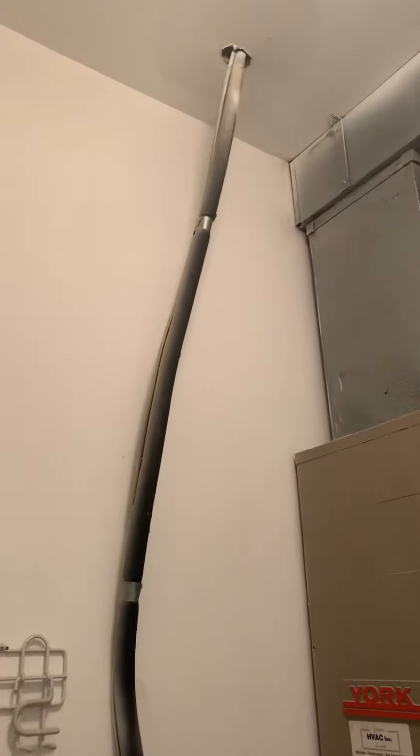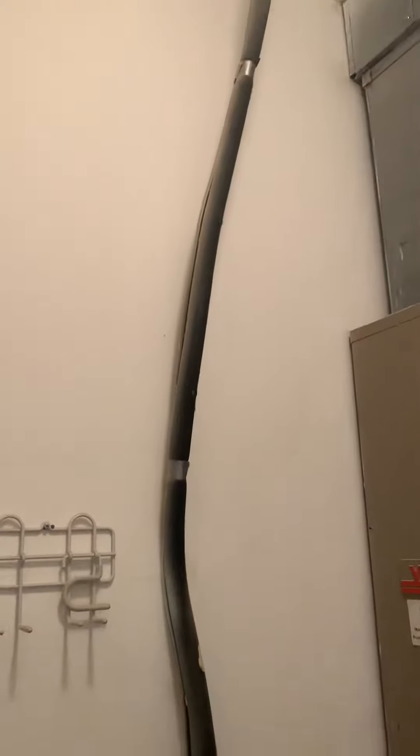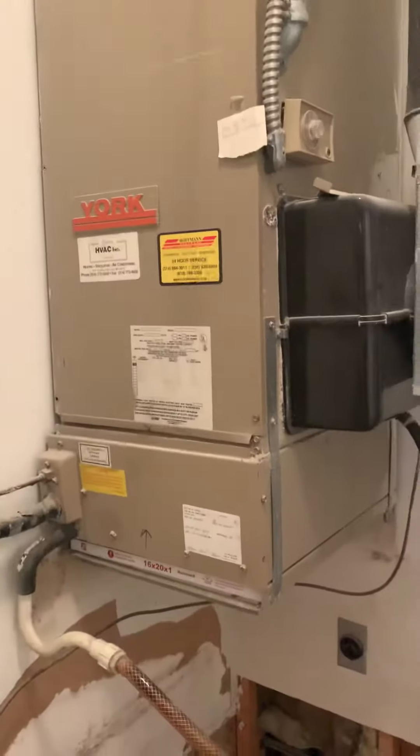Looking at flush placement because the unit's up on the roof. We just want to run this cleaner, probably tighter to the wall — obviously still leaving room for a screwdriver to get in there and take off the panel — but it just runs a lot better.